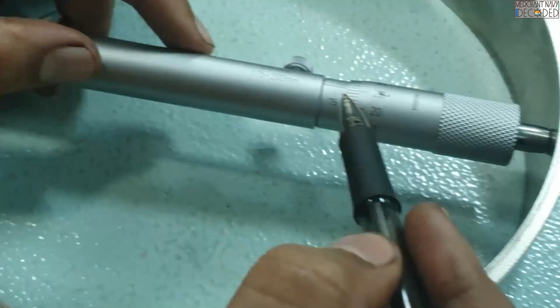And now I do the measurement. How much is it? So guys, the measurement is 175, 176, 177, 178, 178.26. That is the reading I've got right now with the ID of the flame ring.